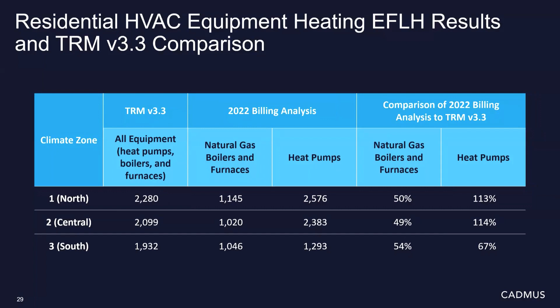The billing analysis derived heating EFLH values for heat pumps are significantly higher than the TRM 3.3 values for climate zones 1 and 2, but noticeably lower for climate zone 3. This could potentially be due to smaller urban homes or homes that do not use their heat pumps as their primary source of heating. We also know that heat pump operation is quite different from boilers and furnaces, and the electric billing analysis likely reflects that added fan and defrost energy use. Electric heat pump heating EFLH values presented here, again, also only reflect the average heat pump customer operation, which is likely a mix of supplemental, primary, and whole home heating.